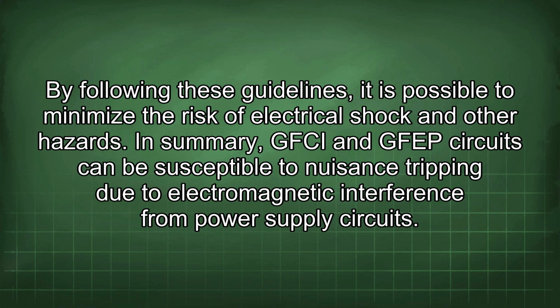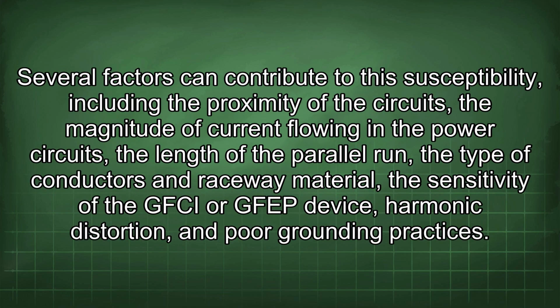In summary, GFCI and GFEP circuits can be susceptible to nuisance tripping due to electromagnetic interference from power supply circuits. Several factors can contribute to this susceptibility, including the proximity of the circuits, the magnitude of current flowing in the power circuits, the length of the parallel run, the type of conductors and raceway material, the sensitivity of the GFCI or GFEP device, harmonic distortion, and poor grounding practices.